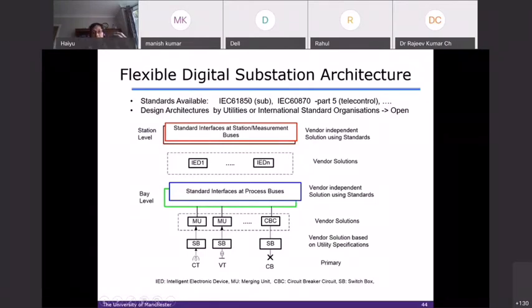So that means it's a standard - we have a standard framework, we design our own architecture, and then vendor solutions come in. They have what's called a merging unit - a digital merging unit, basically analog to digital conversion. Then you have digital to control the breaker, similar for the protection device, measurement, etc. This is the vendor solution. Our role is to design the architecture for that, based on the available standard.